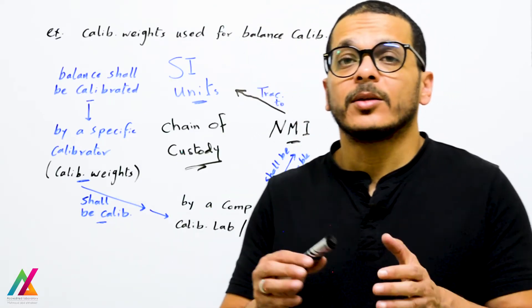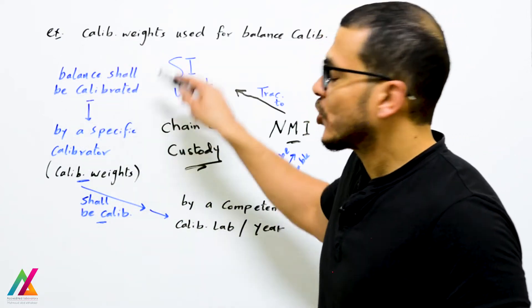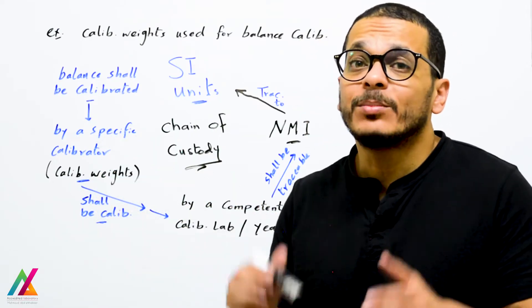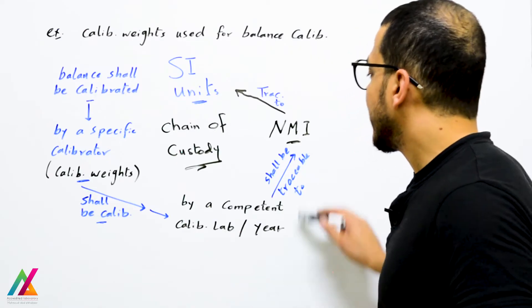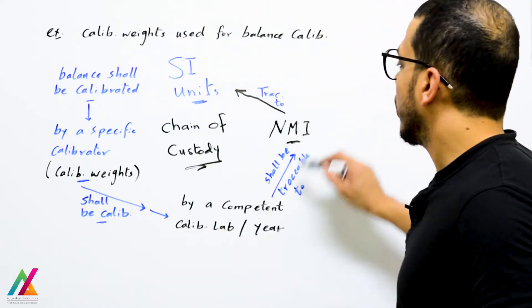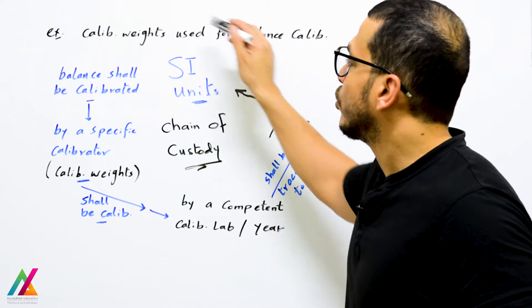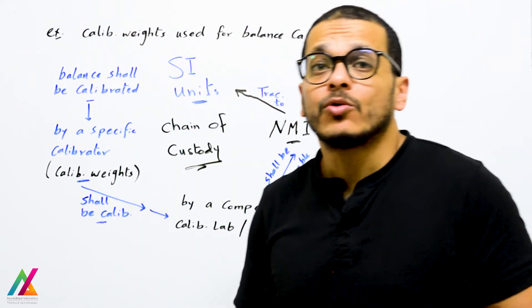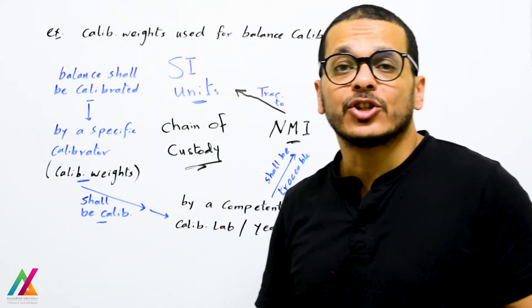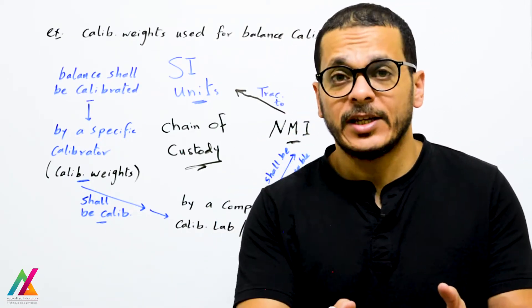As an example of traceability, consider calibrated weights used for calibration of a balance. The balance shall be calibrated using calibrated weights, and those calibrated weights shall also be calibrated — by a competent calibration lab, typically every year. That competent calibration lab shall be traceable to the national metrological institute inside the country, and that national metrological institute shall be traceable to SI units. This is the chain of custody ensuring comparability of calibration to the international system of units.